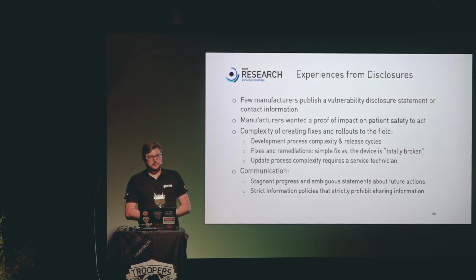And also, there are often contracts where the device is not being patched by the operator himself, but by the manufacturer and some service technician that is coming. And if you imagine that we have 650 hospitals in Germany, and each of those hospitals is using, for example, 2,000 syringe pumps, then that will take some time when you're installing an update with 10 minutes on each device. So that's simply a practical issue you have to handle in the end.